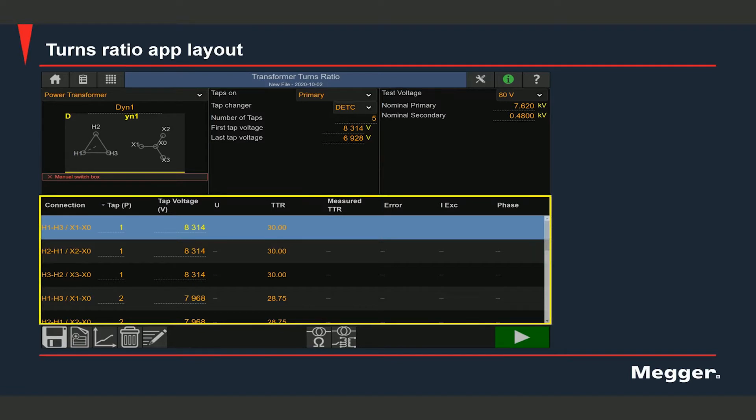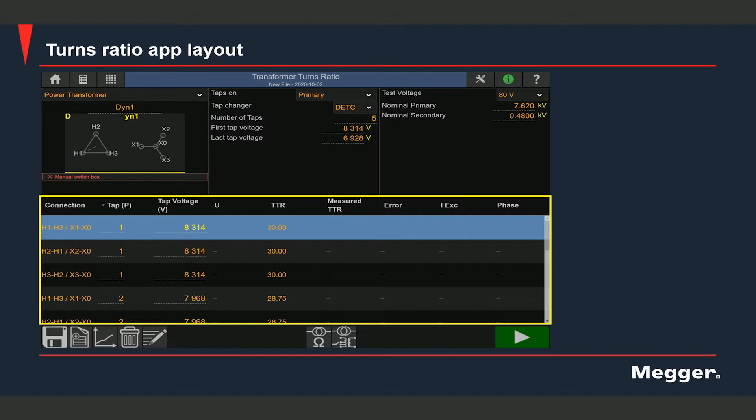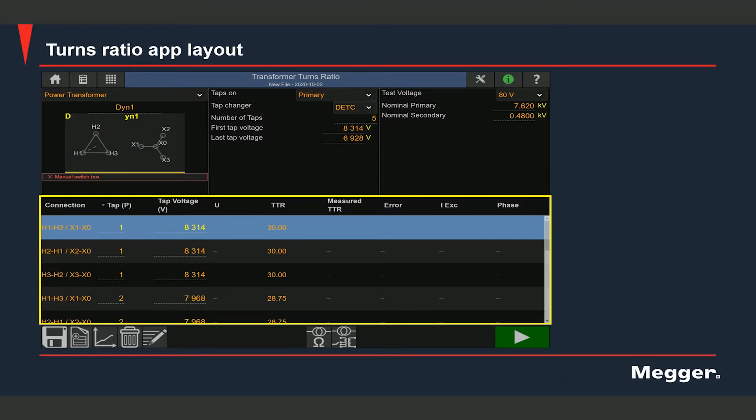This is the test section where you can see the test data. If you start from the left, you can see the connections that would need to be made for testing different phases. You can see the tap position. You can see that there's a column for the corresponding tap voltages. There's a column for the test voltage. And you can also see the calculated TTR values at different taps. And then the last four columns is where the test data would populate. That includes the measured turns ratio values, the percentage error with respect to the nameplate TTRs, excitation current which is the current which the transformer draws when you run each measurement, and phase, which is the phase deviation between the applied voltage and the measured voltage.